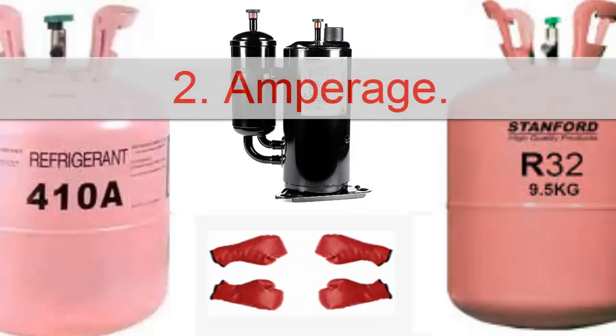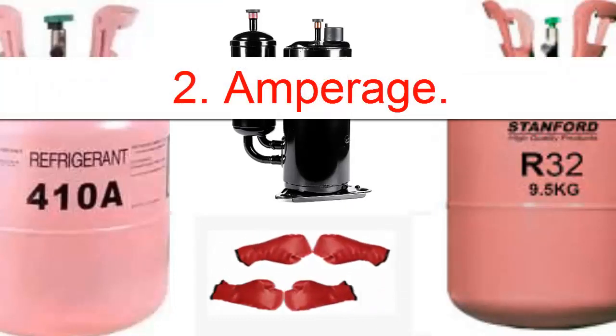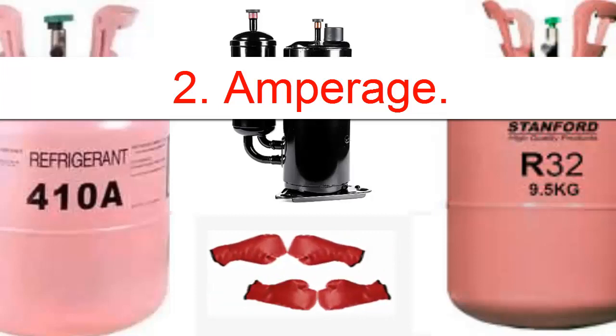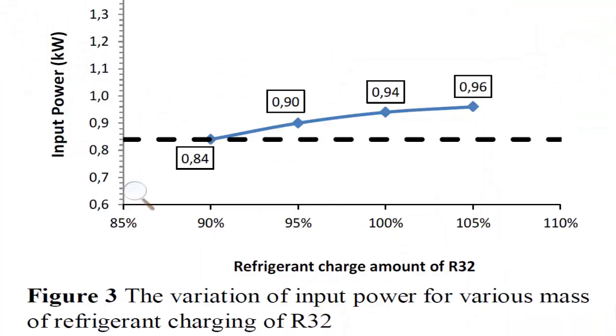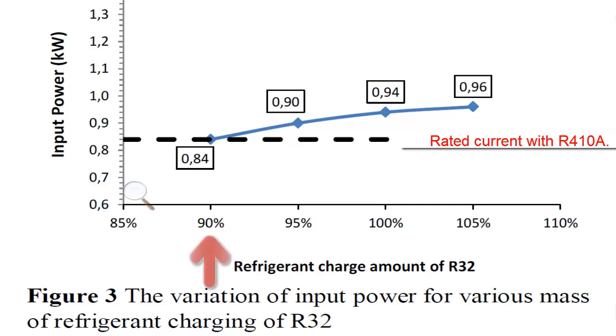2. Amperage. The electrical current of the compressor will be affected by the change from R410A to R32. Ideally, the nominal electrical consumption of the compressor should be maintained, representing the equipment's characteristics when operating with R410A. Studies have shown that to achieve this nominal consumption value, the equipment should be loaded with only 90% of the weight indicated for the R410A charge. A load value exceeding 90% will lead to an increase in the compressor's electrical consumption beyond the nominal value, which can result in abnormal compressor heating and a loss of equipment lifespan. This is because changing to R32 will lead to an increase in the mass flow rate of the refrigerant, resulting in an increase in discharge pressure. This rise in discharge pressure will cause an increase in electrical current and, consequently, in input power.